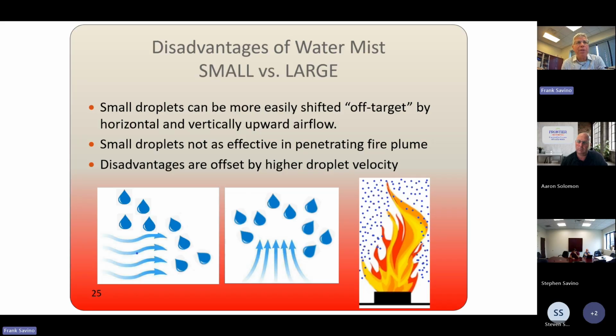So the smaller droplets are more easily shifted off target by, say, horizontal airflow. Small droplets are not as effective at penetrating a high intensity, very large fire plume. They may get blown up, okay? But if they're going into a fire plume, they're going to gasify and start cooling it, and then other droplets are going to come in behind to penetrate to the seat of the fire. And the other thing is that some of the disadvantages are also offset by the higher pressure and high velocity that a lot of water mist systems have to penetrate.